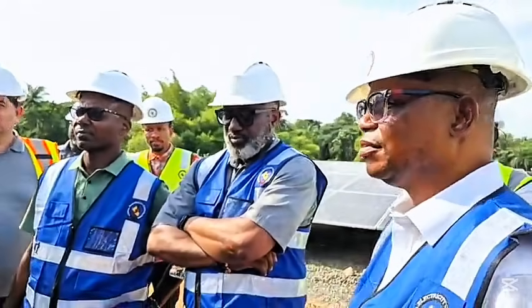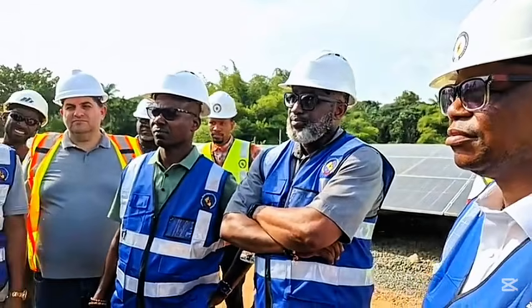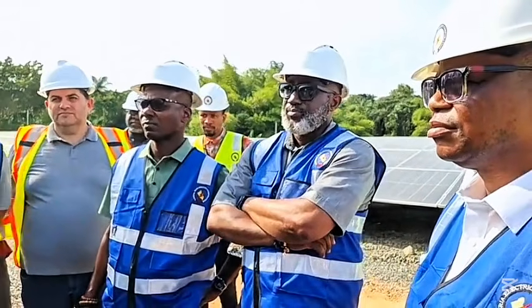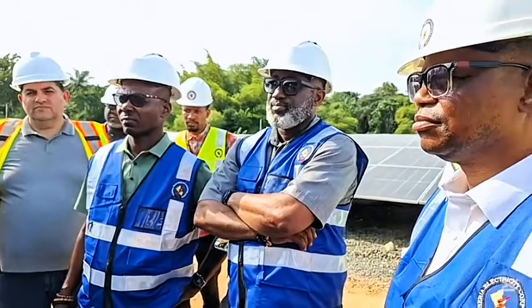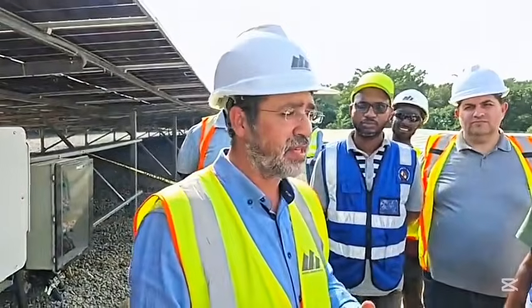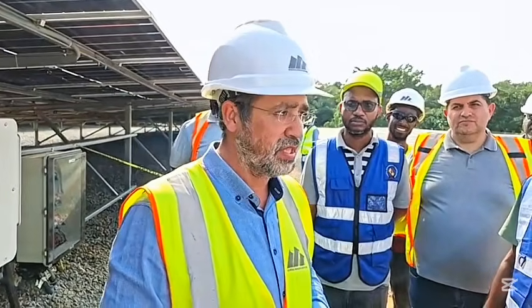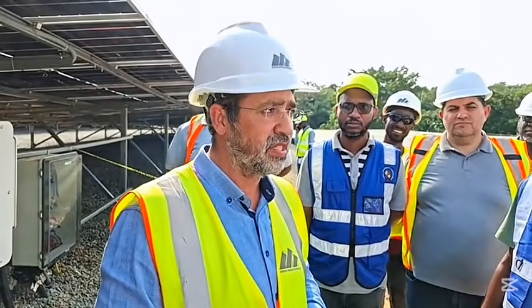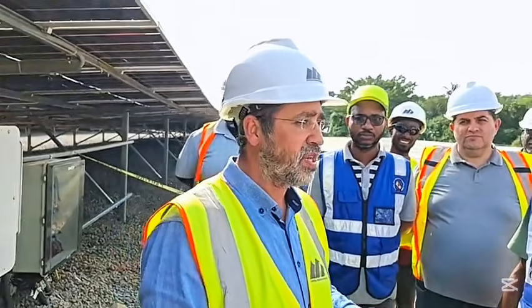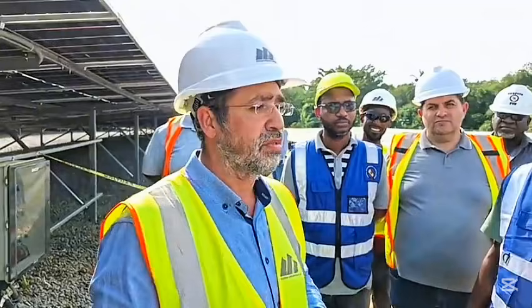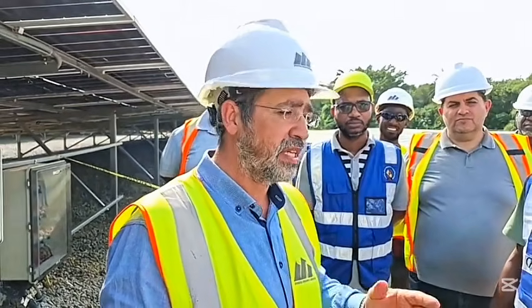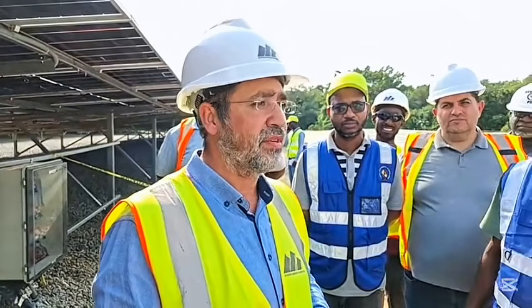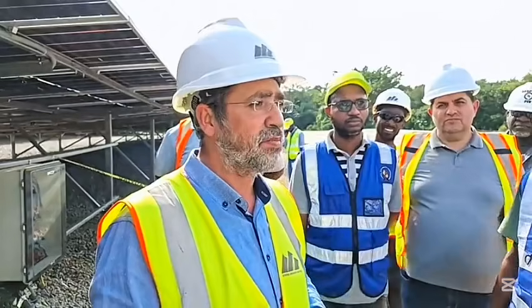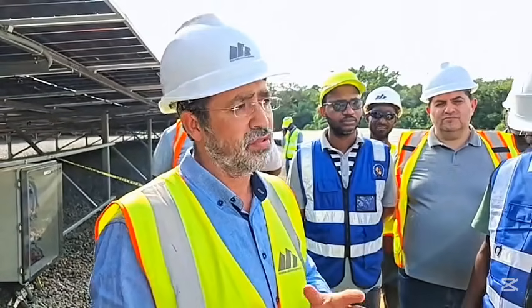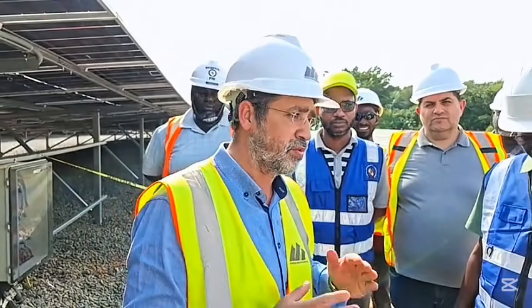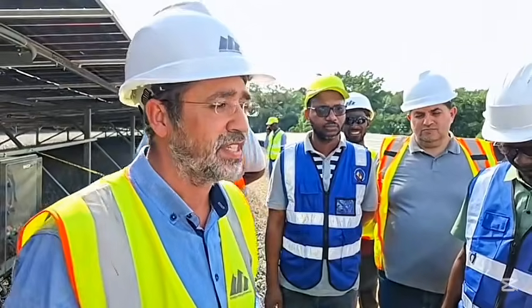Of course, on the existing substation side, we have installed a power transformer, 24 MVA, and the maximum power we are able to reach is 16 megawatts AC. As we implement stage 1 and stage 2, stage 1 is 16 megawatts AC, and later we will add 10 megawatts peak for stage 2, topping up the transformer to reach the maximum of 24 MVA.